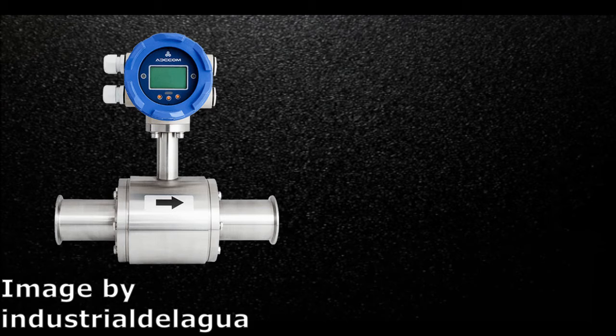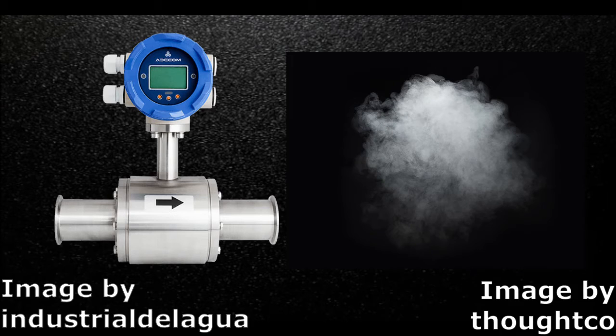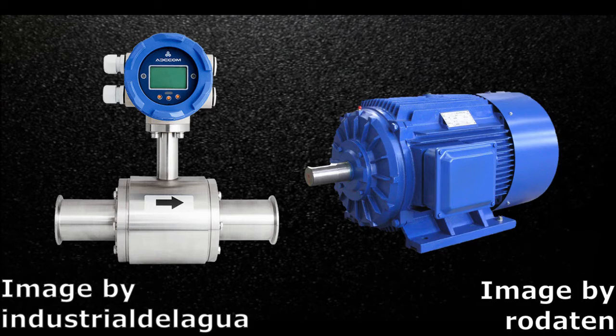The length of the cable between the element and the receiver should not be that long. This type of meter does not serve to measure the flow of gases, since their conductivity is much lower than that of the liquids. Magnetic meters are sensitive to noise signals, for example, those caused by high-power electric motors near the meter, as they generate a magnetic field that can overlap the flux from the meter itself. The reference voltage system is responsible for eliminating this type of noise.